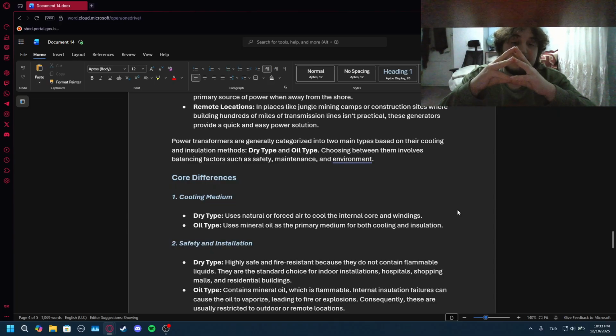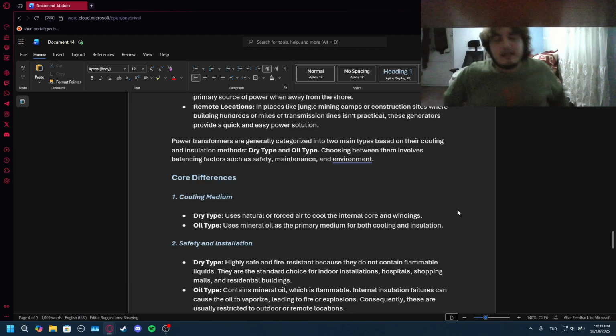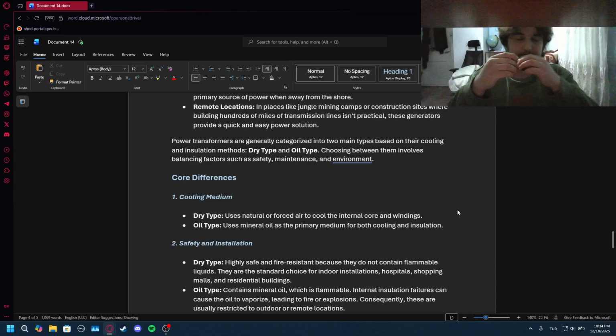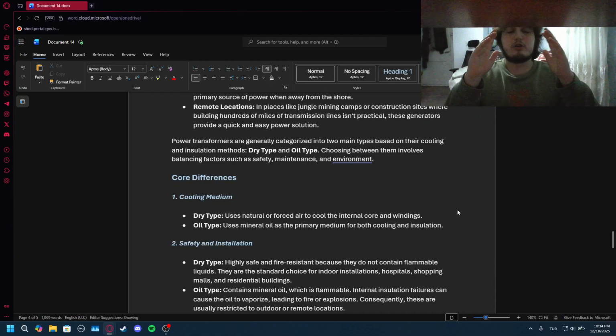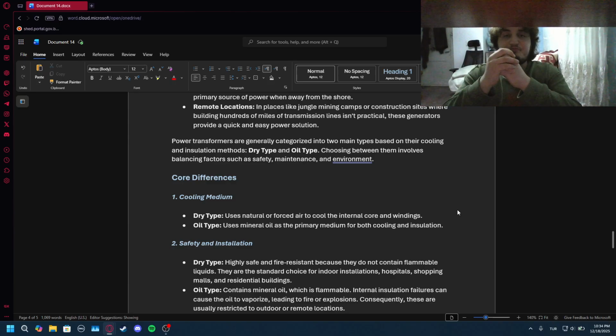But the dry type, yes, it gets rid of that because it only has air inside, and even if it breaks down, the most that's gonna happen is the windings are gonna burn, but not in the sense of burning, they're just gonna melt, and the transformer is just gonna go off in a circuit breaker. But in the other one, there's a chance of explosion, and if I remember correctly, like 80% of almost all of the transformer failures are basically caused by winding failures, and inside an oil type this can cause explosions, obviously.